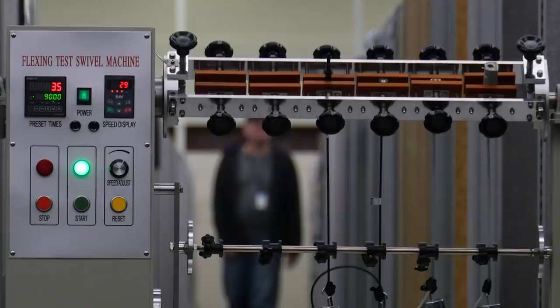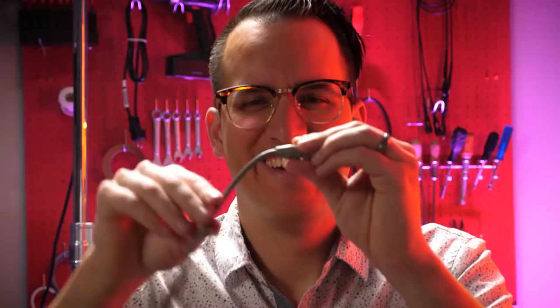The first test we're going to look at is a probe flexing test. We'll clamp the probe in the flip-flopper and it will flex at that strain relief point thousands of times. We also do solenoid encoder testing where we have a robot that goes back and forth thousands of times. I always pictured we had someone in the basement who just kind of flexed the cables — that was the old method.